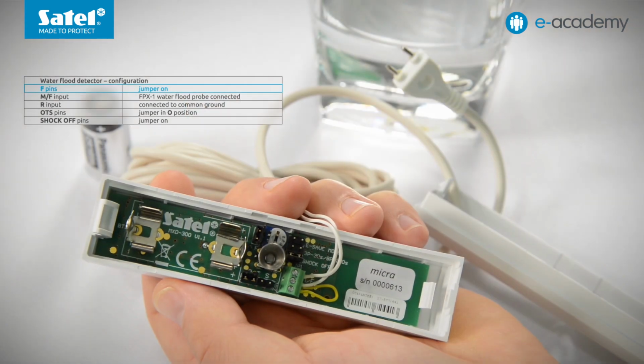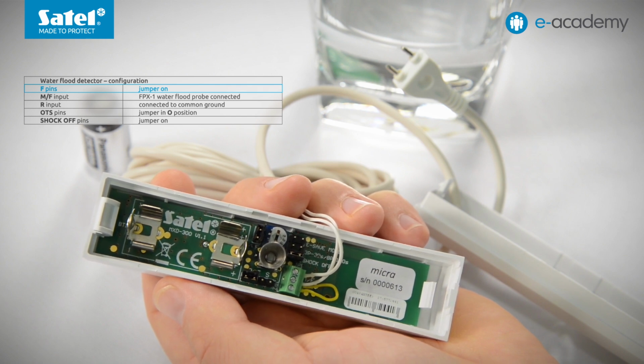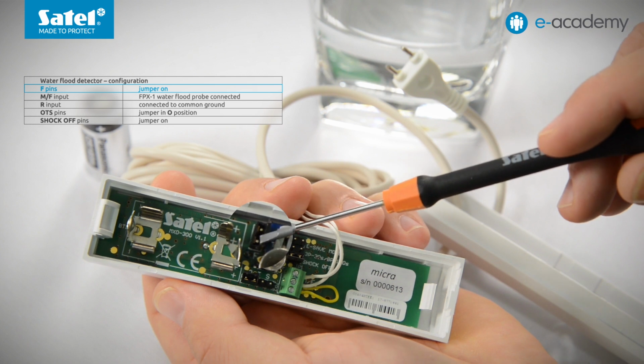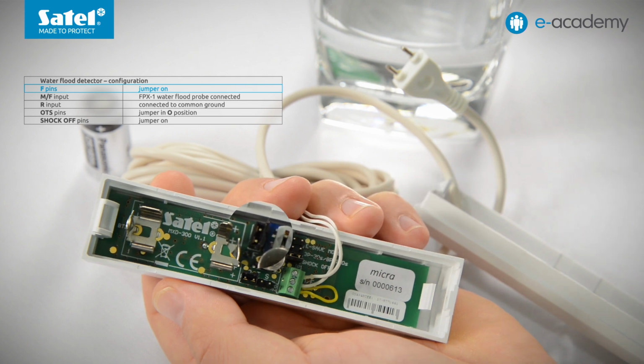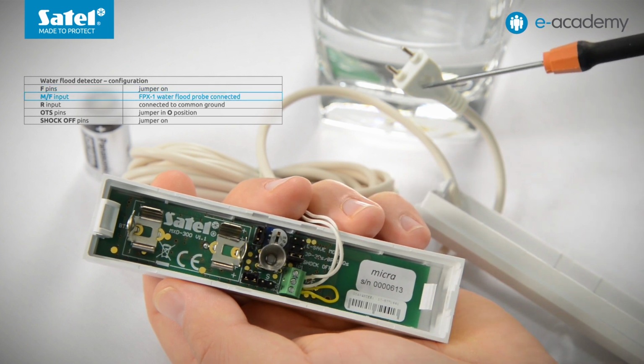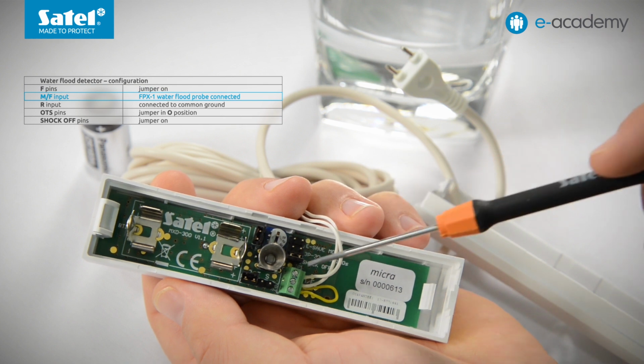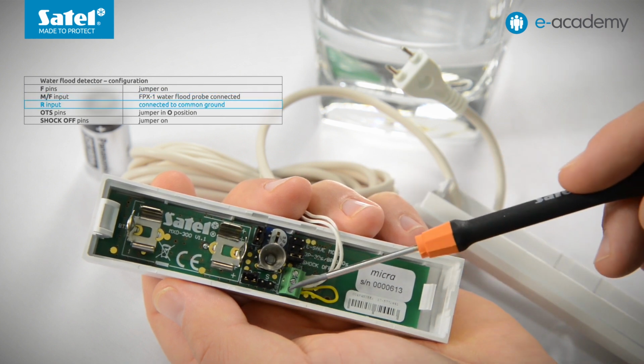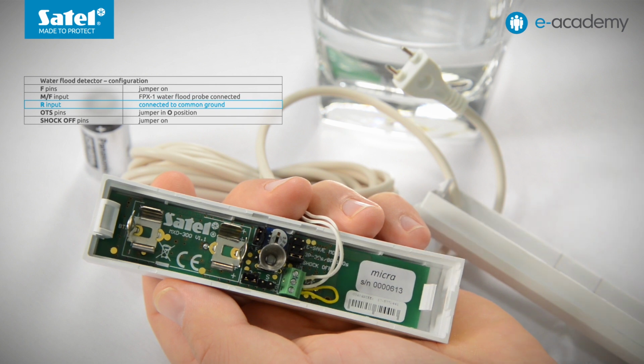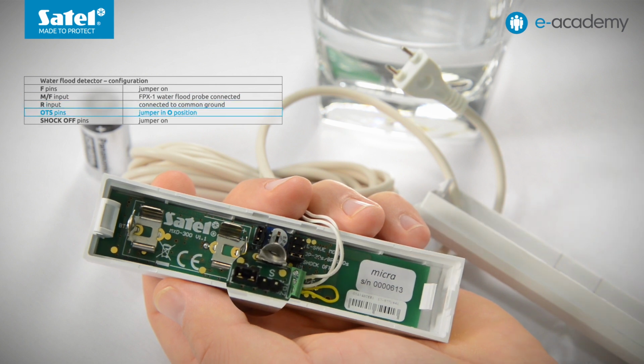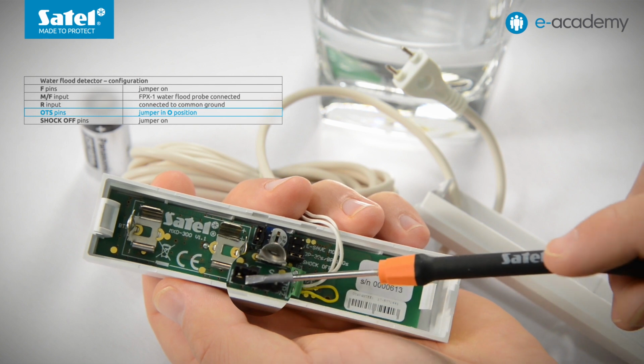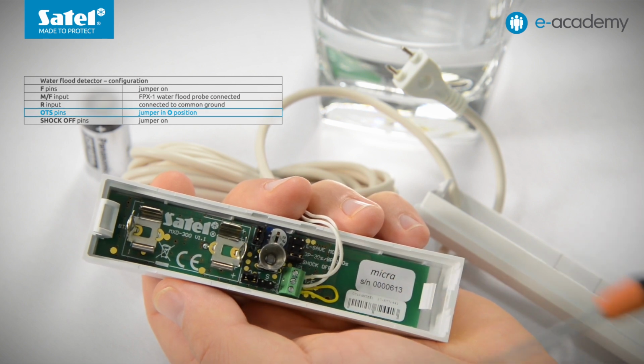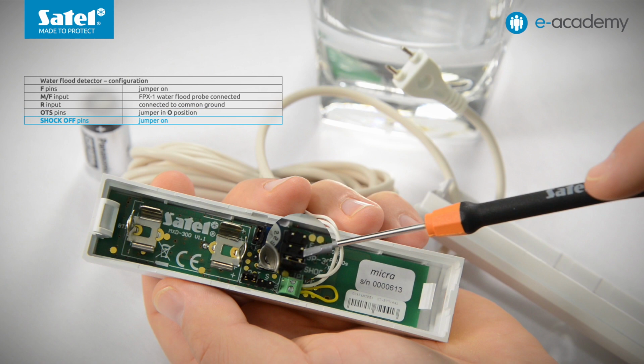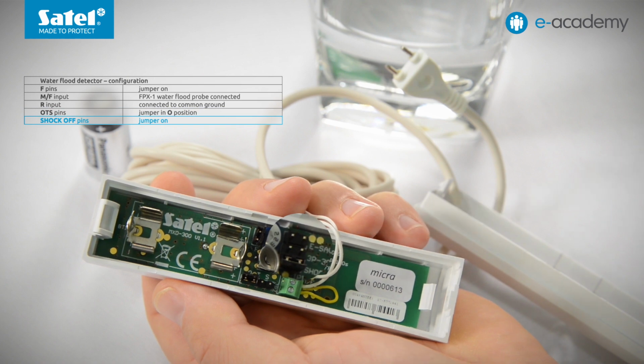Let's take a look at the last configuration. For the MF input to be ready to work with the flood probe, there must be a jumper placed over the F pins. The FPX1 probe, the key component of the flood detector, is connected to the MF input, while the R input is shorted to ground. The reed switches are turned off, so the jumper is placed over the pins marked O. The same applies to the shock sensor, which is to be disabled, so the jumper is placed over the shock off pins.